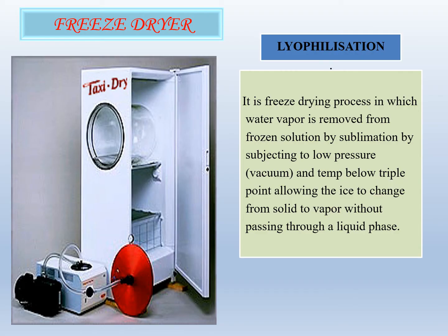In this part 2, we will see freeze dryer and fluidized bed dryer. Freeze drying method is also called the lyophilization method. It is a freeze drying process in which water vapor is removed from a frozen solution by sublimation, by subjecting it to low pressure and temperature below the triple point, allowing the ice to change from solid to vapor without passing through a liquid phase.